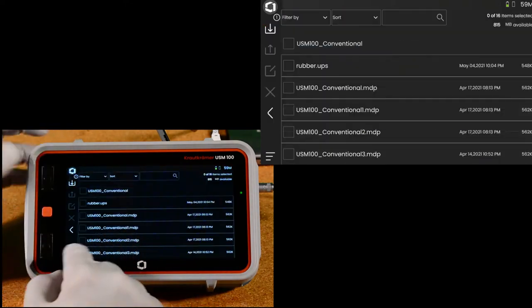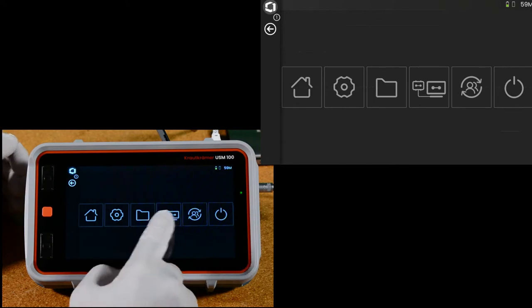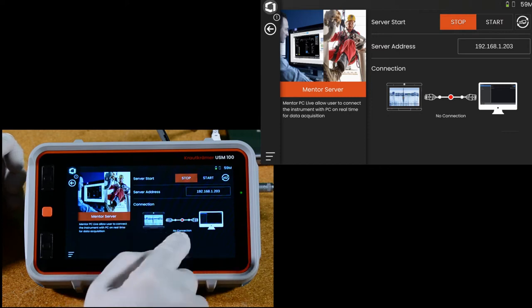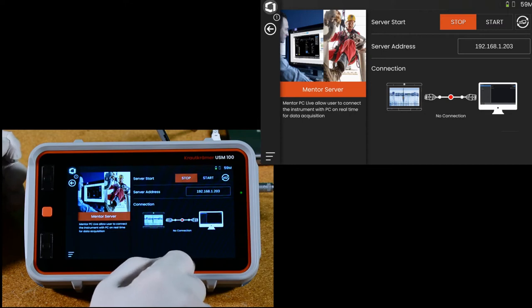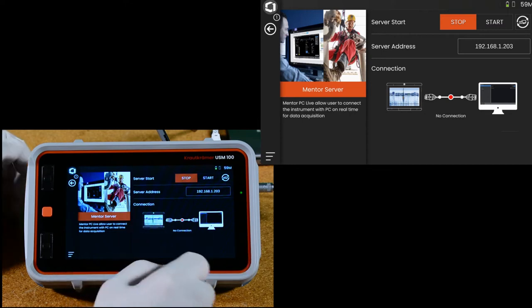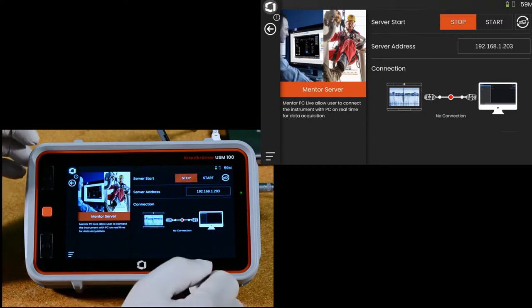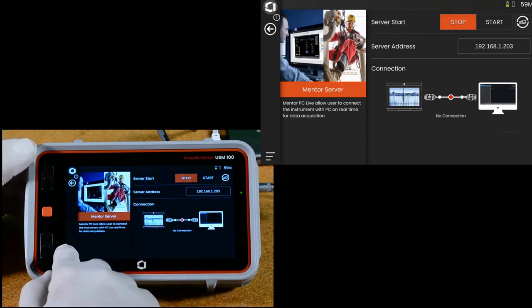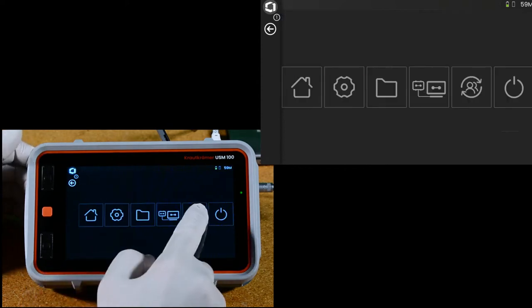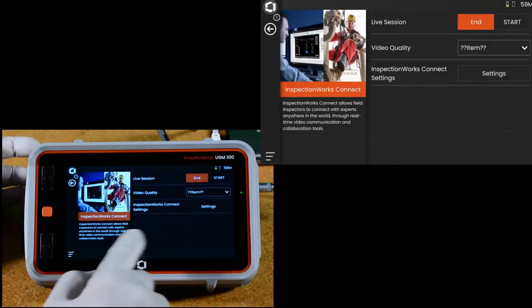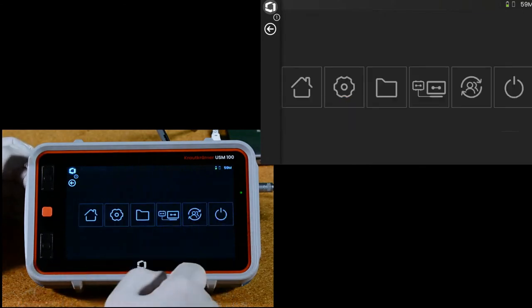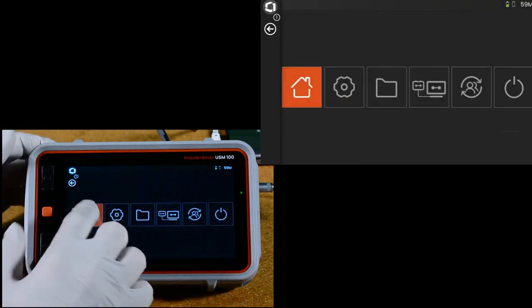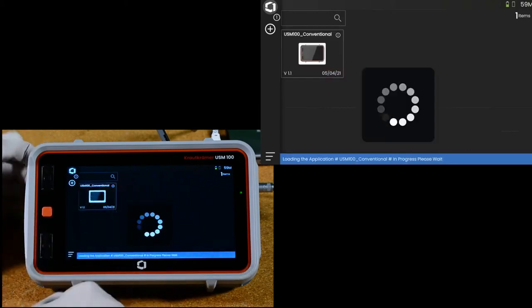So if we go back to our settings panel, the next icon is our setup for USM100 PC Live. This is PC software that can link through Ethernet that basically provides all the functionality on the instrument on the PC, with the instrument being the front end for ultrasonics. We have Inspection Works Connect, long distance internet connectivity, and a shutdown icon. Let's go back to the desktop and we will launch our app.